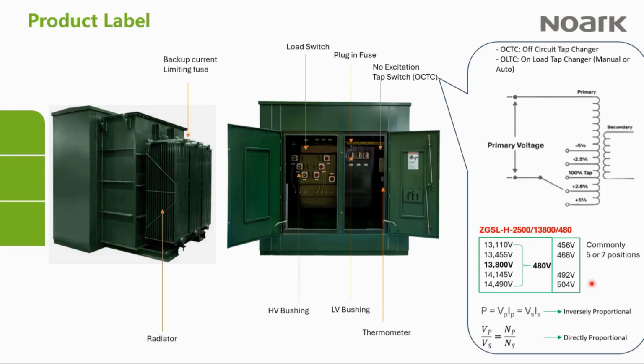The other type of tap changer that we have is the 7 position. So we have 5 position, we have 7 position. All these we use. This particular pad mount transformer has an off-circuit tap changer. We also have what we call the on-load tap changer. The off-circuit tap changer means that if there is a fluctuation in the voltage and you need to change the tap, they have to de-energize the transformer first. Then they go right here and do the tap change. So you have to de-energize first. But for the on-load tap changer, you don't need to do that. You can actually do the tap change while the transformer is still energized.